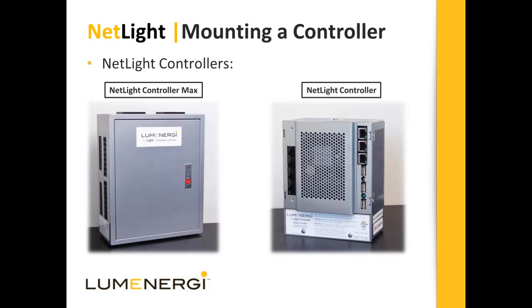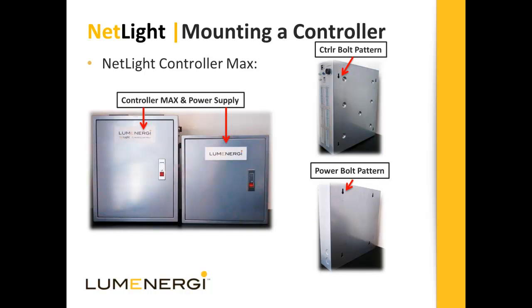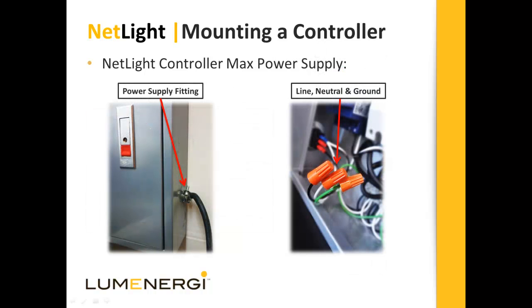Lumenergi provides two lighting control units, the NetLight Controller Max for larger scale installations, and the NetLight Controller for smaller scale installations. To mount the NetLight Controller Max and power supply, use number 8 round head machine screws to secure the units to the wall using the bolt patterns located on the back. To set up the power supply, remove one of the punch outs in the lower right hand side of the unit and hardwire a power line to the capped wires inside. Wiring must be in compliance with Article 300 of the National Electrical Code.